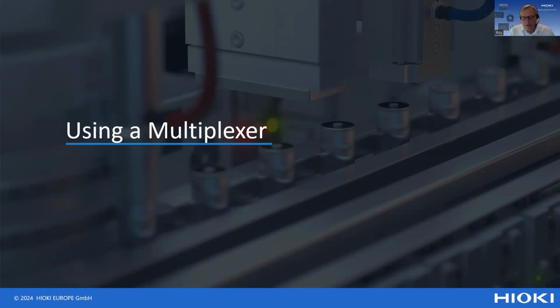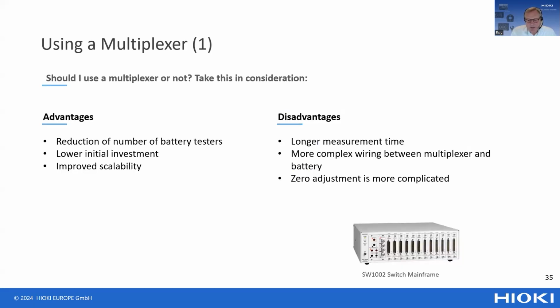Okay, then we go to the third influence, and that's whether or not to use a multiplexer for AC/IR measurement in the production line. It's up to you, and it depends on different things. Using a multiplexer will reduce the number of battery testers and therefore can reduce the initial investment. Further, the use of multiplexers increases the flexibility. If the number of batteries that you need to test is increasing, the only thing that you have to do is just add another multiplexer card in the mainframe, and you have more channels that you can measure with.